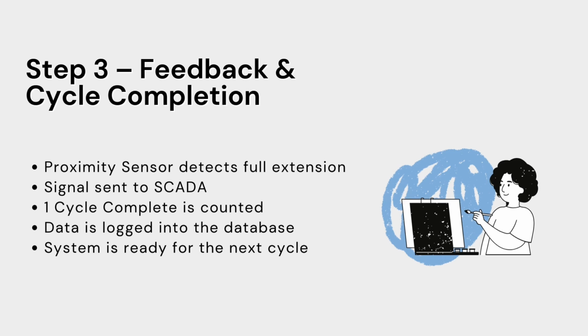As for the third slide, which is step 3, feedback and cycle completion. Once the cylinder reaches its full extension, the proximity sensor is triggered. It sends the feedback signal and tells SCADA that the movement was successful. The system then counts one completed cycle and stores the data in the database. After that, the system is ready to repeat the test.